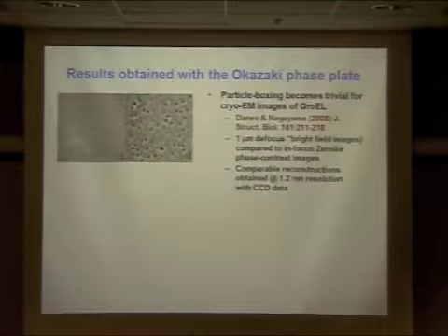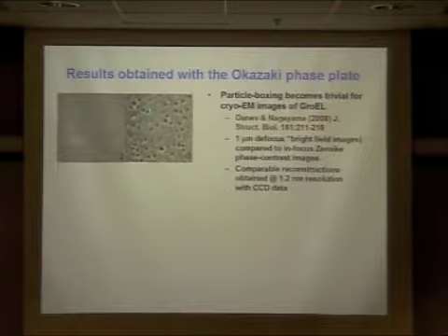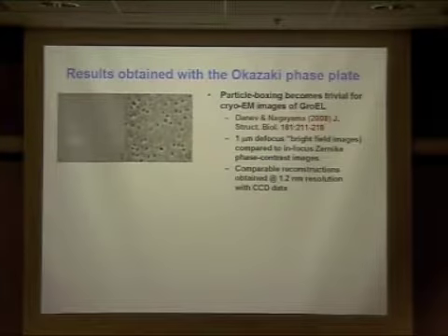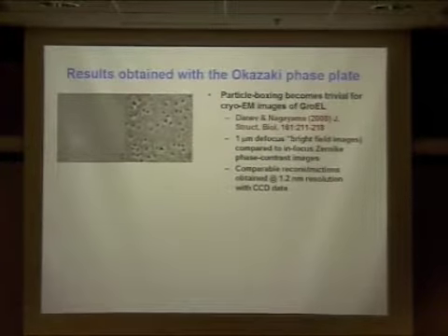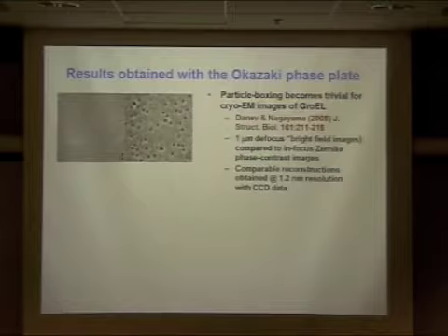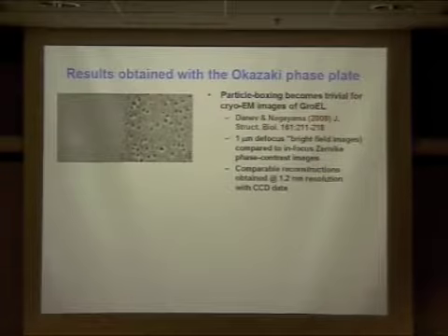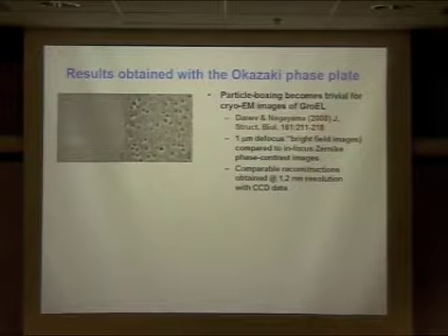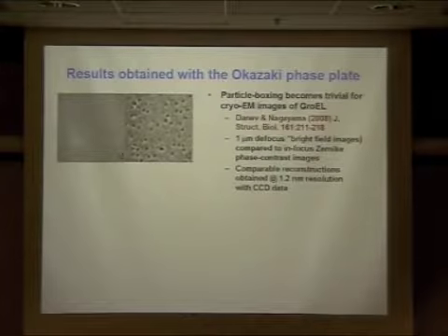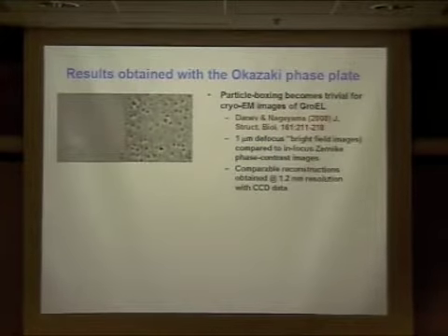Couldn't you have a much thinner phase plate? Yeah, I think that's the right way to do it, because then the white halos become much less noticeable as well. Yeah, I agree. So these objects are not, strictly speaking, weak phase objects. They're already fairly small, GroEL particles. You'll see it even worse when I show you TMV on the next slide. With carbon film, it's difficult to make it thinner because it has to be self-supported over the entire aperture. And it has to be even thinner to begin with when you drill a hole, because it's very important to do the wrapping step. I haven't explained why. I can, but it is important.